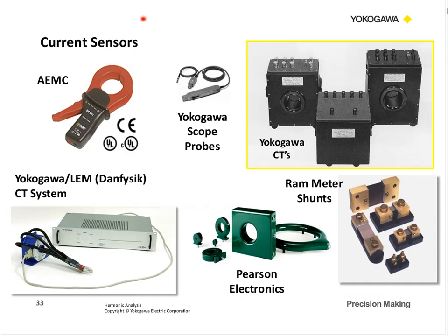So we talk about current sensors. This is very important. Generally, we can take in the voltage direct up to 1,000 volts, so that's pretty much defined by the instrument specifications and the bandwidth. But the current sensors, we can't bring in maybe all the high current, so we've got to go through some type of current sensor. So these are very important to consider in your measurements. Some of the shunts. Now these are good for DC. It's just a precision resistance that we're putting in line. So those are DC, not good for distorted waveforms and high harmonic content.